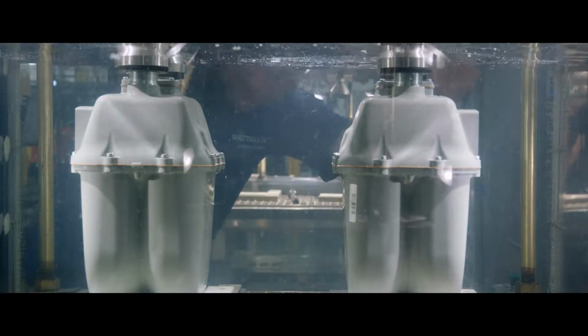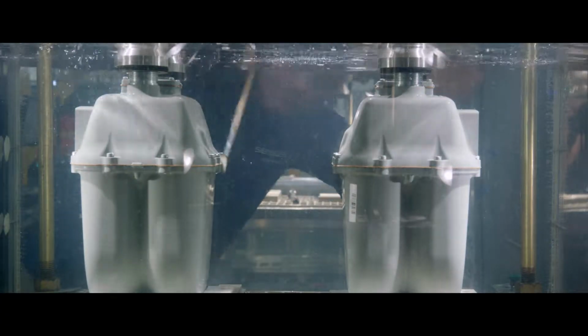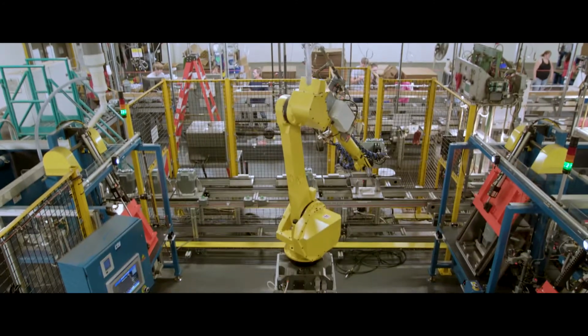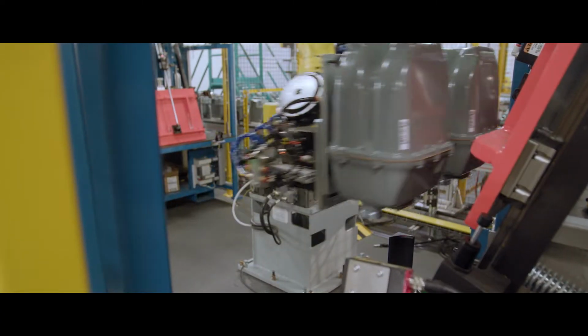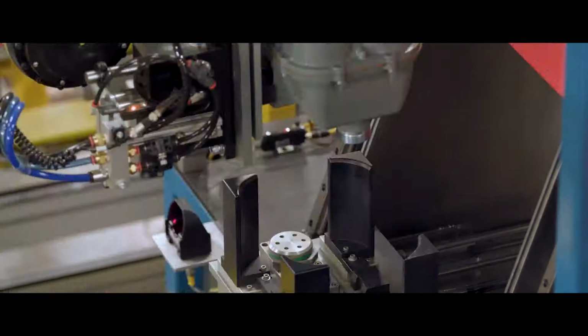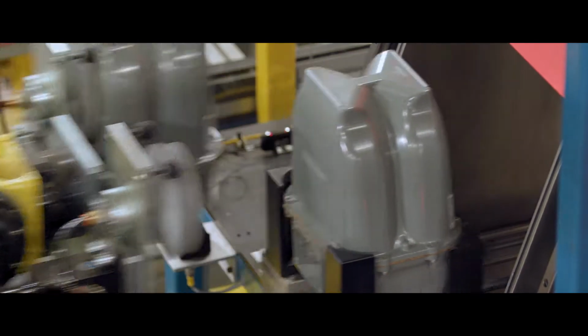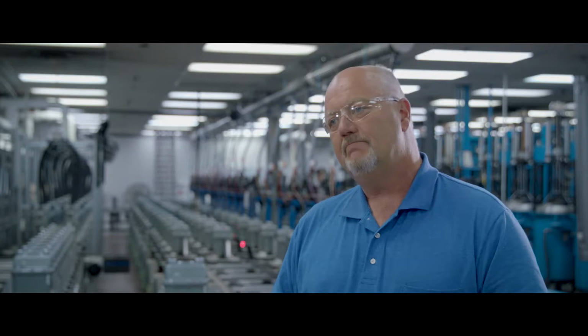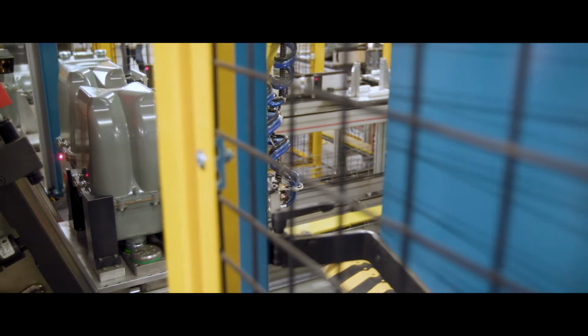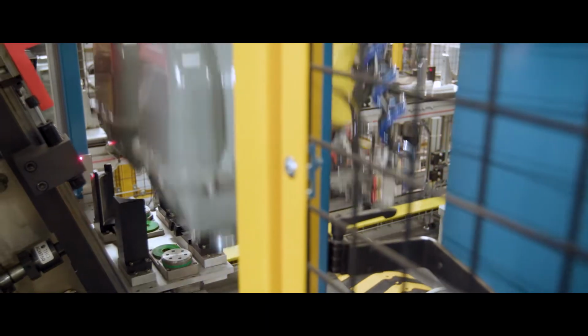When you perform water testing, you're pressurizing the vessel, submerging it in water, and you're looking for a bubble. So visual acuity is very important. With helium, it's objective. We use a mass spectrometer to measure small quantities of helium that potentially exit the meter. We can measure that quantity and equate that to a volume. We're able to set up thresholds that would be undetectable by the human eye.